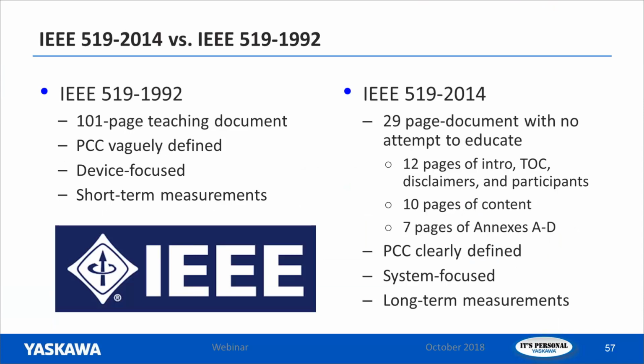So a little comparison here between the standards. In the 1992 edition, it was a 101-page teaching document with the point of common coupling vaguely defined. I don't believe it was intentionally vague, it just worked out that way. It ended up being interpreted to be device focused, which is not the intent, and it covered short-term measurements. So they cleaned this up. They decided they wanted to straighten everything out in 2014, so they reissued it as a 29-page document with no attempt to educate. 12 of those pages are introduction, disclaimers, participants. 7 of them are annexes. It's boiled down to 10 pages of actual content. Even I could probably digest and understand the 10 pages of content.